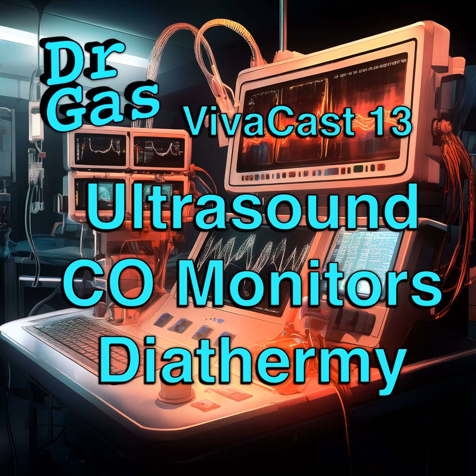Whereas... What is the... Oh, sorry, Tom. I was just going to say, the pad is large. What's the difference between that and the tip of your diathermy? So the surface area at the tip of the diathermy is very small, so the concentration of current, the current density, is much higher at the tip of the diathermy, which is what allows it to cut tissues and coagulate and things like that. The bipolar diathermy doesn't use a connector on the patient at all. If you imagine a pair of forceps where the current passes between the two tips, this means that there's reduced risk associated with the travel of current through the patient.